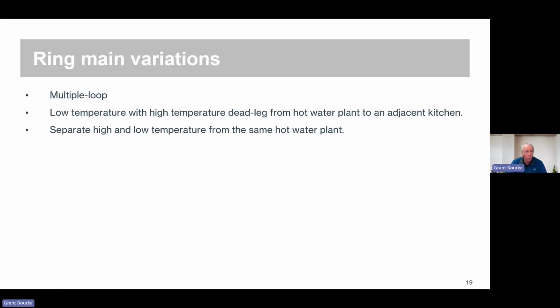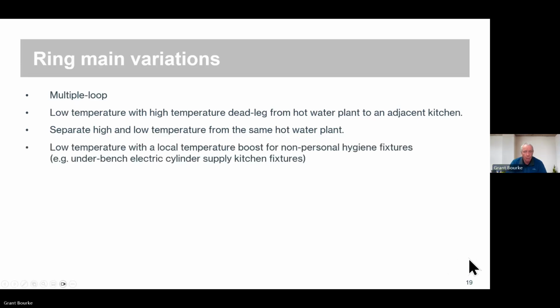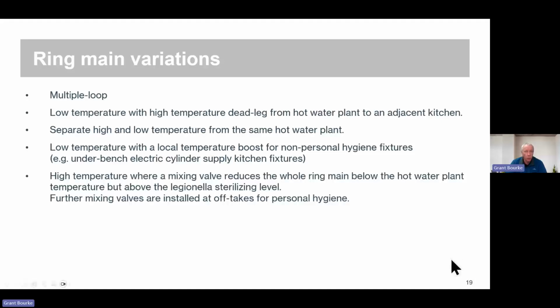Similar thing, we could run a high temperature loop to the kitchen and scullery and a low temperature loop around the sanitary fixtures for personal hygiene. We saw this one, we can have a low temperature and have a boost cylinder at some fixtures. We can have a high temperature ring main, and we might decide that our hot water plant is making water that's too hot for the pipes we've got.